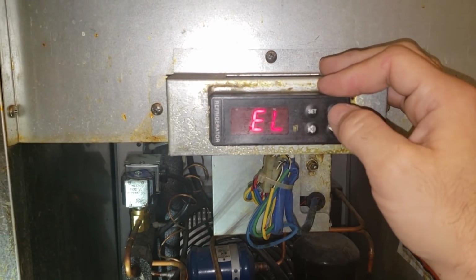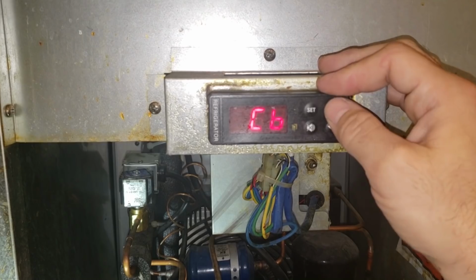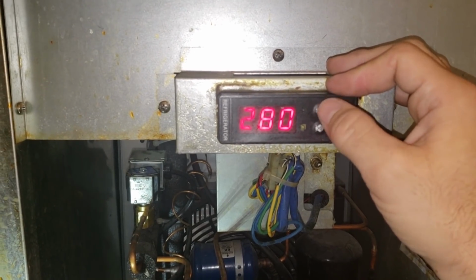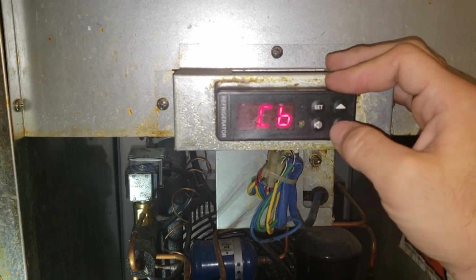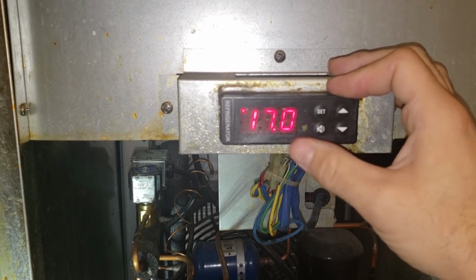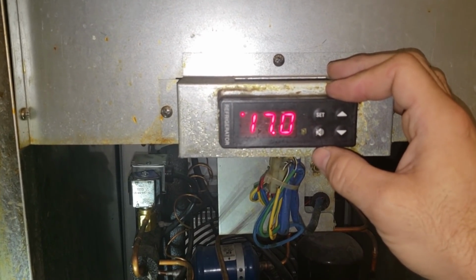So we're concerned with CB and EL, and those sensors should be reading pretty close together. So we've got one reading 28, and we've got one reading 17, so 11 degrees off.